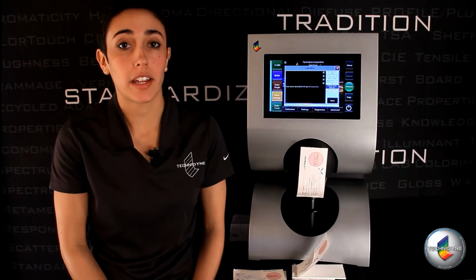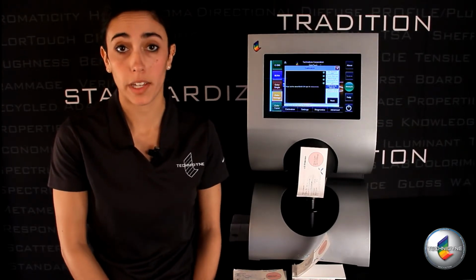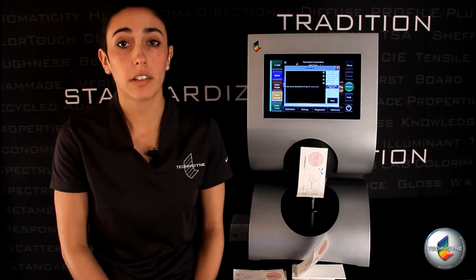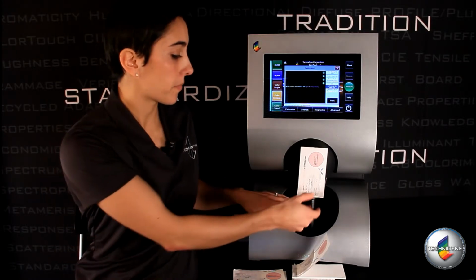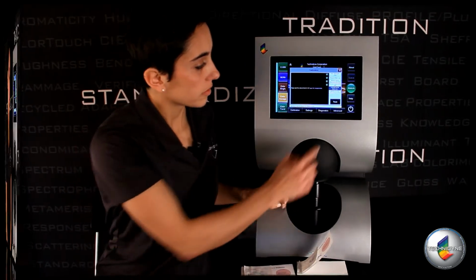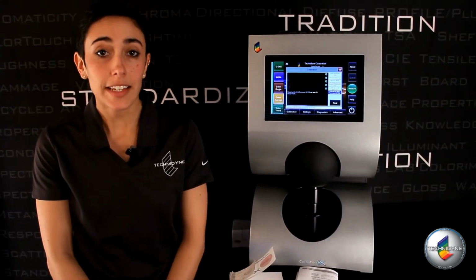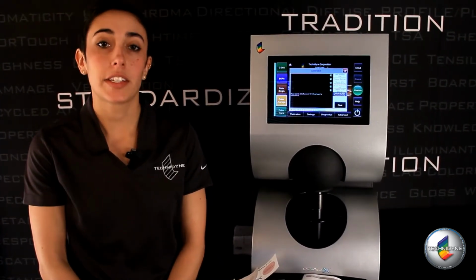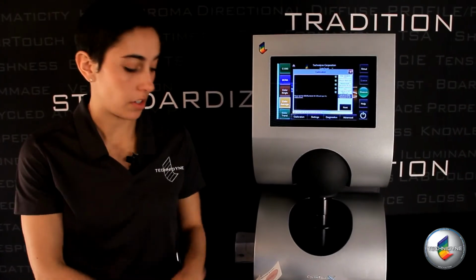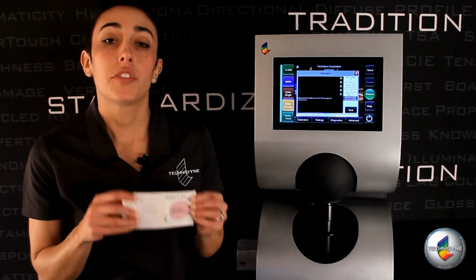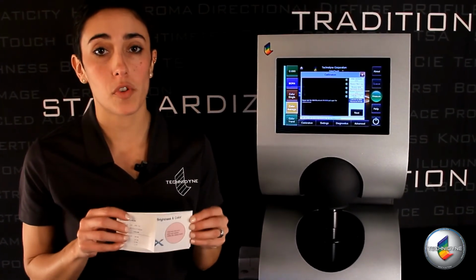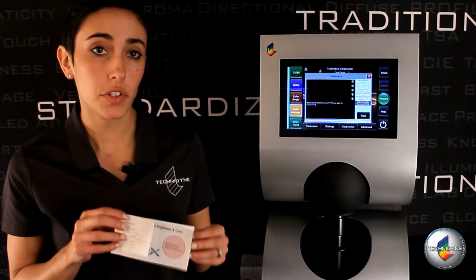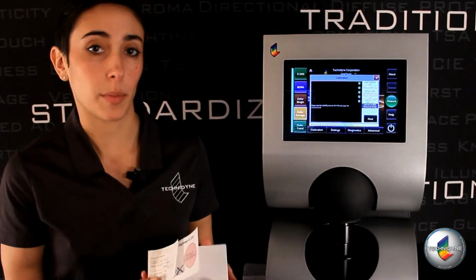Once the primary and fluorescence calibration are completed, the software will instruct you to load the black cup again. This will establish dark level under this new calibration. The last step in the calibration sequence is to load the non-fluorescent 90 standard one more time. During this process, the ColorTouch will perform an evaluation of the internal swing-in standard and complete the calibration process.